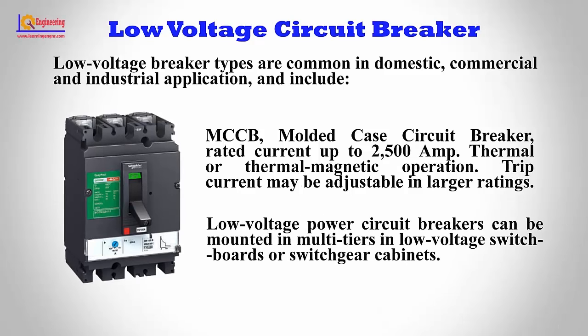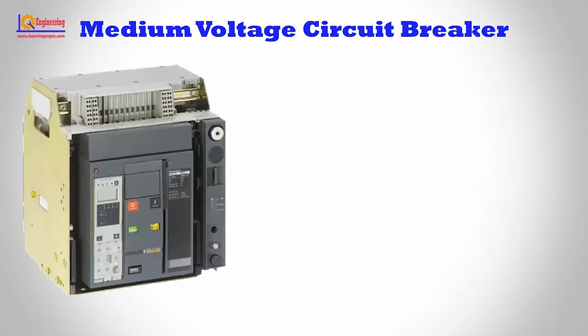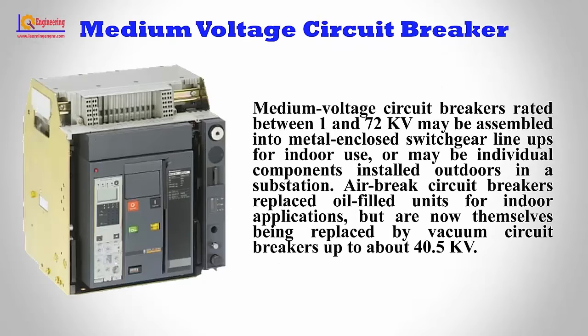Low voltage power circuit breakers can be mounted in multi-tiers in low voltage switchboards or switchgear cabinets. Medium Voltage Circuit Breakers, rated between 1 and 72 KV, may be assembled into metal enclosed switchgear lineups for indoor use or may be individual components installed outdoors in a substation. Air break circuit breakers replaced oil-filled units for indoor applications but are now themselves being replaced by vacuum circuit breakers up to about 40.5 KV.